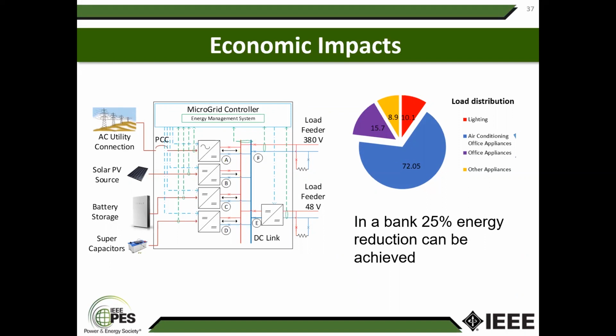Remember, the banks operate during the daytime where solar PV is available, and the modern air conditioners are inverter driven. So there is a DC bus where you can directly use DC, removing the AC to DC conversion stage. Your lighting is LED, so you don't need an AC bus. Right now with the AC bus, you need an AC to DC converter and power factor correction.